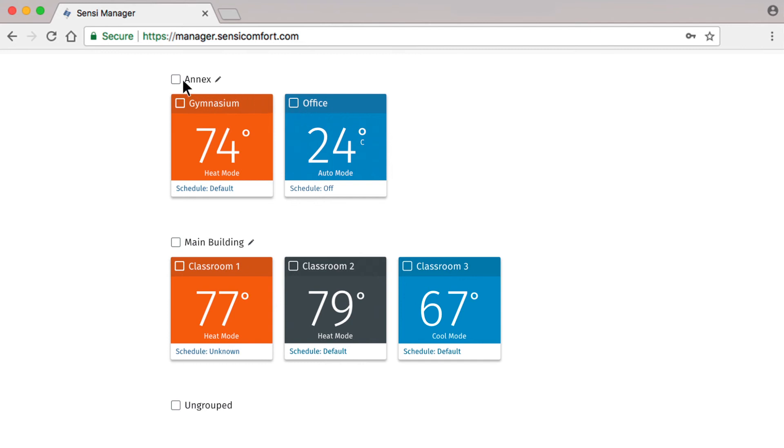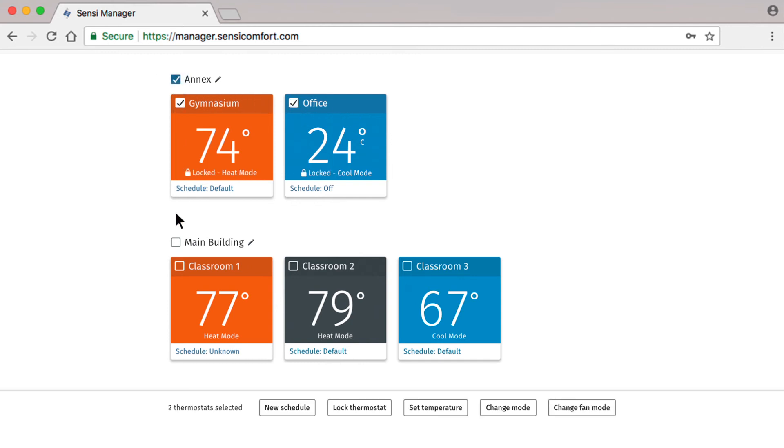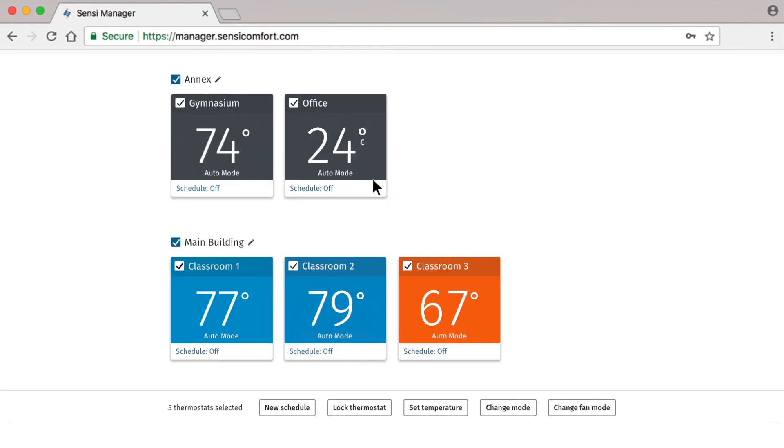In this case, you would select all the thermostats by choosing each group, then select the Change Mode button. Select all of them to Auto, then choose your ideal set points for the moment. Again, you'll get a reminder that scheduled thermostats will follow a schedule after this temporary override.